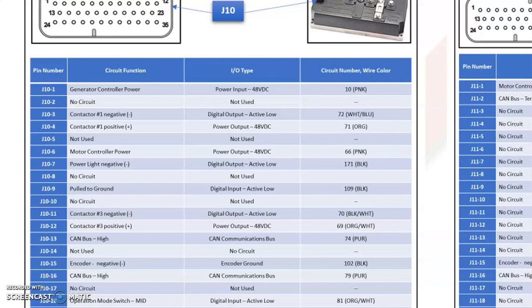Pin number 6 is the power out of the generator controller going to the motor controller. So the generator controller actually powers the motor controller. Pin 7 is the auxiliary light that's mounted next to the fuse box. That's the power for that. Pin 9 is the ground for the speed control switch. So each of the 4 positions, this is the ground for those. Pin 11 is the other contactor, listed as contactor 3 here. Pin 11 is the negative, and pin 12 is the positive power for those contactors.